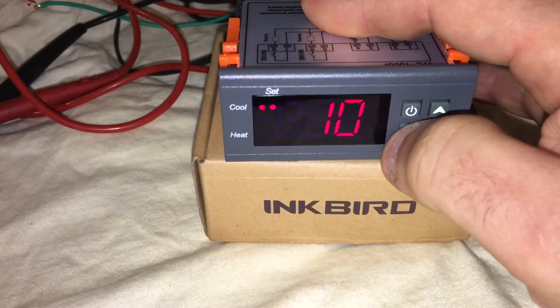Okay, and then I want to do a differential set of - let's say if we're controlled by evap, controlled by evap temp - so we set it 20 degrees evap, and then about a 19 degree for our differential. So I want the evap to pull down to 20, with a differential of 19.